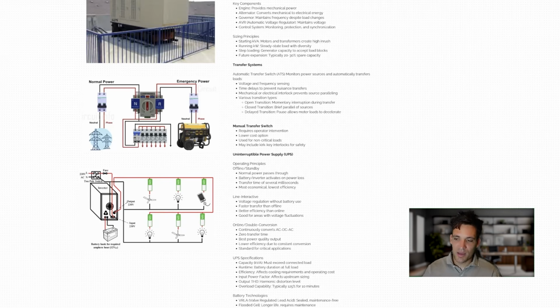The second type of backup and emergency power supply we can have is the uninterruptible power supply. An uninterruptible power supply is basically a set of batteries where you have your incoming power. Depending on the configuration you choose, you then have your battery bank and the outgoing power. When the incoming power drops out, the batteries begin to provide power to your system. That's how emergency lighting systems would operate. Again, you can have really big ones that back up a whole range of systems, or you can have standalone ones that are connected to appliances.